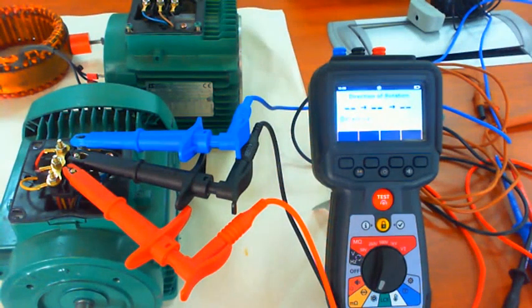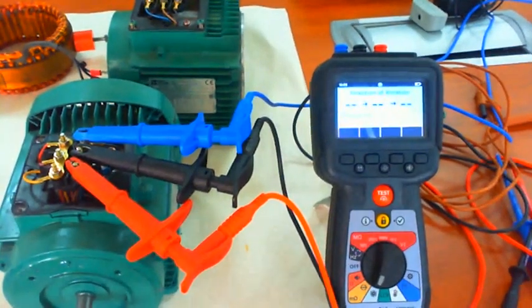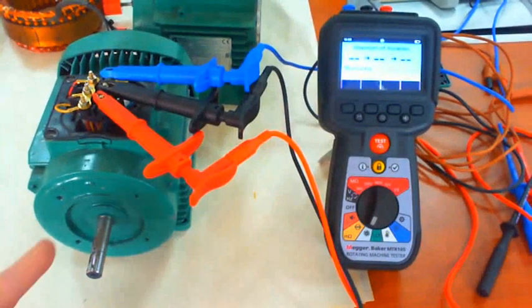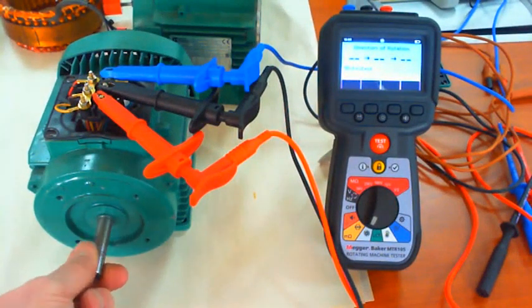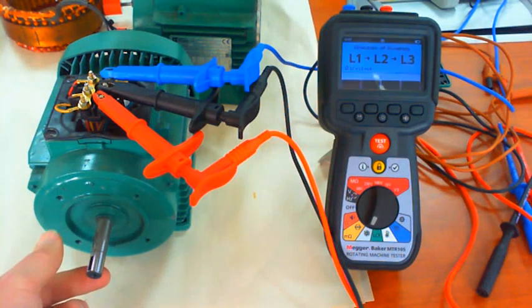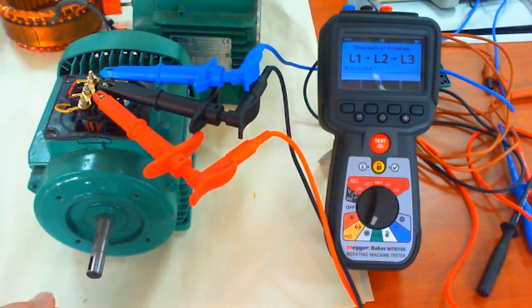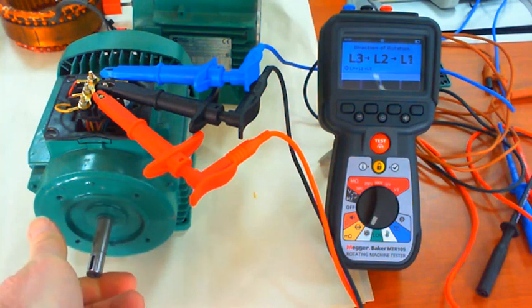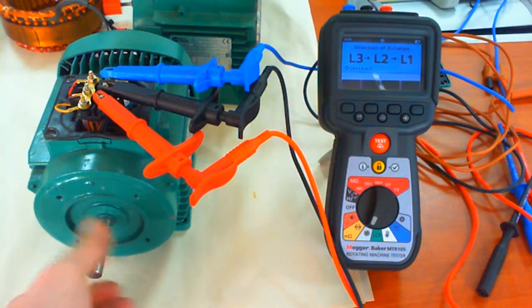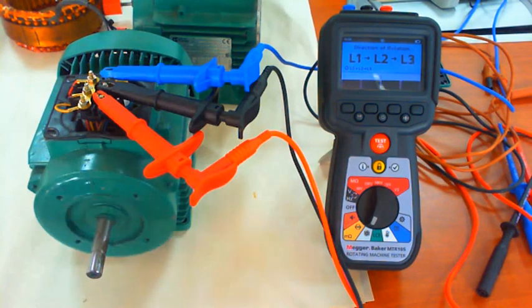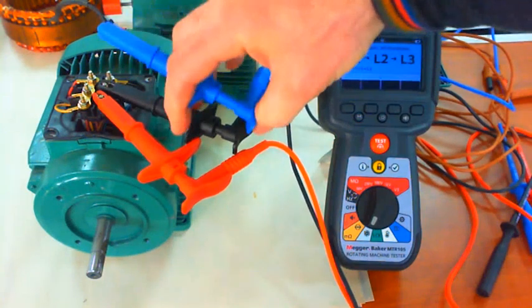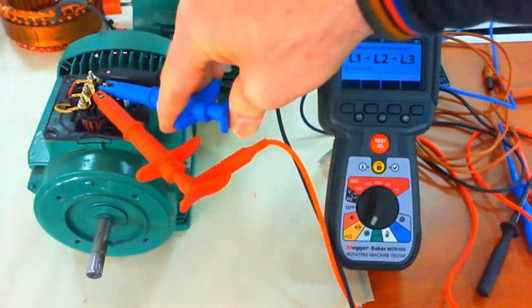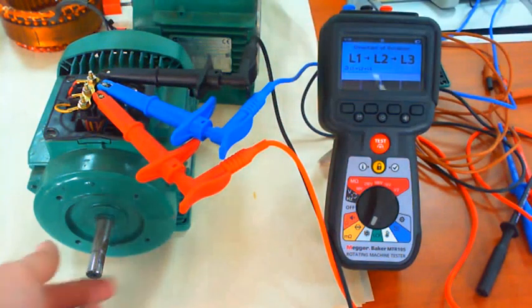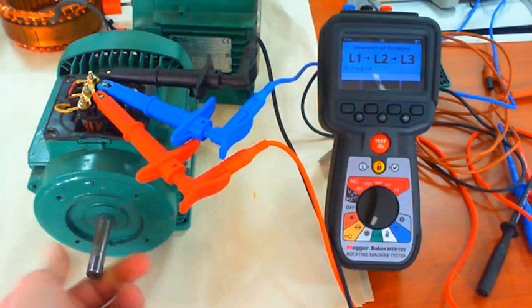It's not displaying anything yet because we need to rotate the shaft. So let's say we want the motor to turn in the clockwise direction. If I turn it clockwise, then you see the display L1, L2, L3. If I turn it in the anti-clockwise direction, it will reverse: L3, L2, L1. Clockwise, L1, L2, L3. Of course, to change direction, you just reverse 2 phases on your power supply or on your motor connection. If I now turn clockwise, I should get L3, L2, L1.